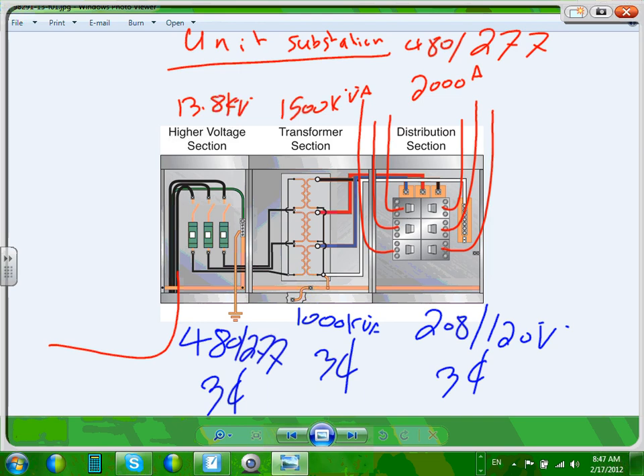I want you guys to look at a substation like this. It has three compartments. One compartment for the whole low voltage distribution section, one compartment for the transformer, and one compartment for the high voltage. It could be either the top coming in for utility type, the bottom coming in for us. So you take a 480 feeder into a certain area, and you put your transformer as well as your distribution panels and the feeder all in one big panel. You bust them together. Who cares? This design is much cleaner, nicer, used in hospitals, sport arenas, and so forth.